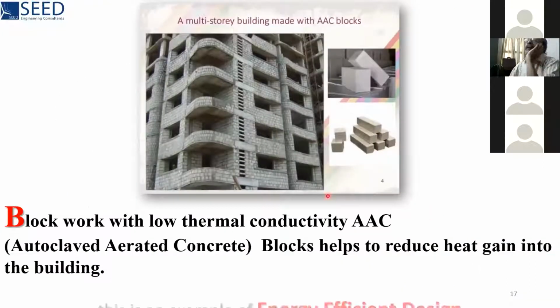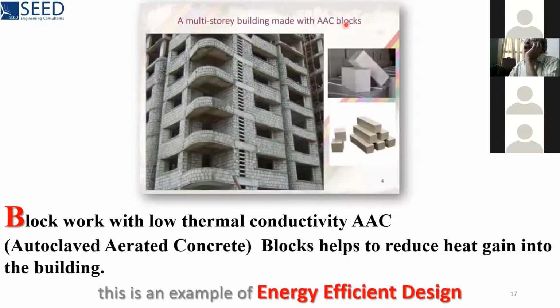See, this is a building constructed by AAC blocks, autoclaved aerated concrete blocks. Blockwork with low thermal conductivity, AAC block helps to reduce heat gain into the building. When we reduce heat gain into the building, your air conditioning load is reduced. Consequently, your electricity bill also comes down. Okay. Now, using such materials, low thermal conductivity material, is a correct move in the direction of energy efficient design.